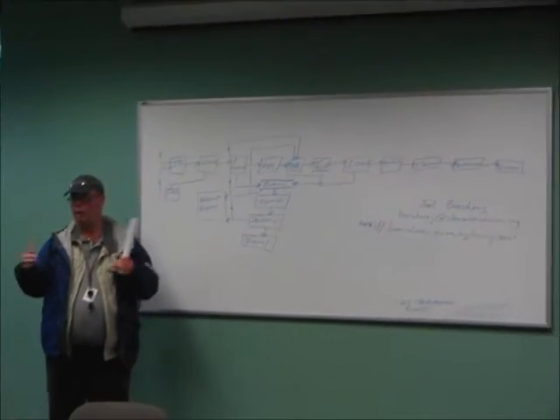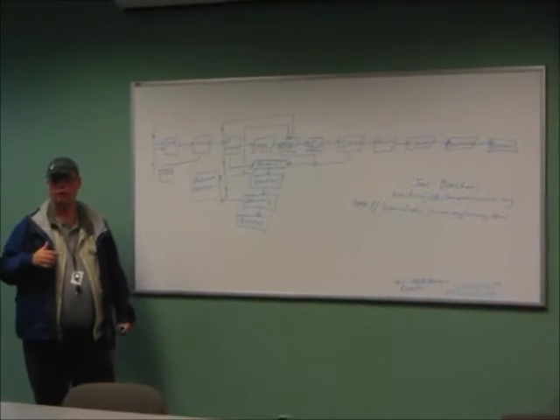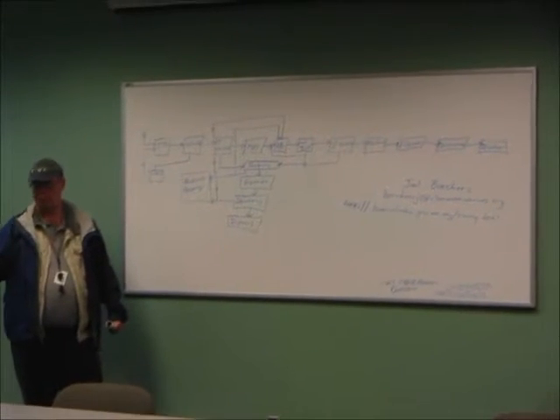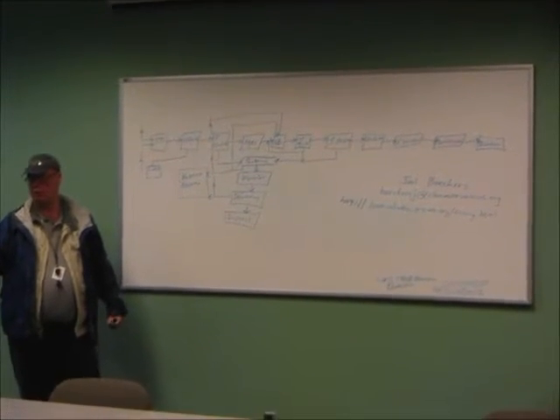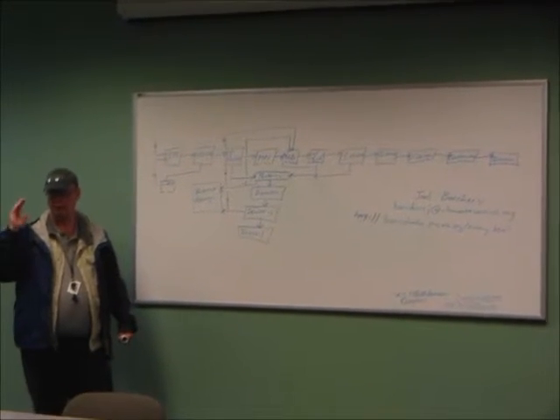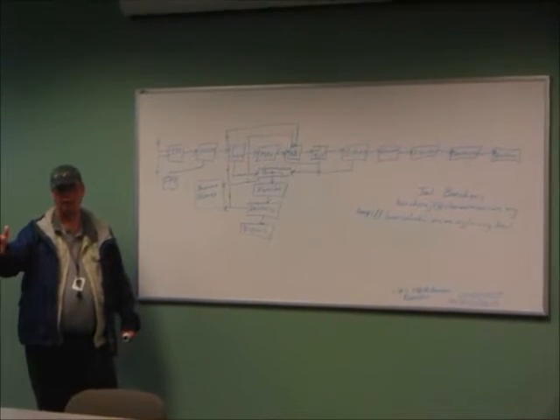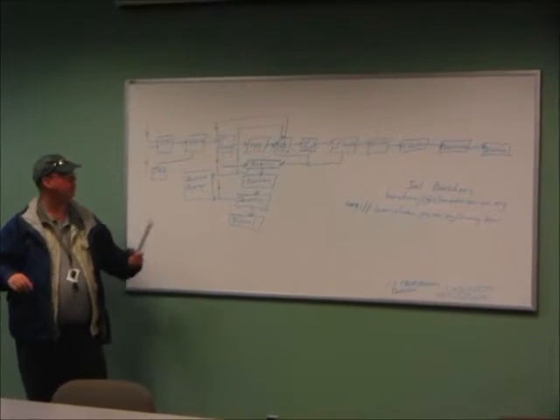We used to split the flow by weirs to 3 aeration basins, and when we added the 4th one, we just didn't quite have enough head to split them evenly. So what we did is we raised the flow up a little bit, and then we could meter the flow to each aeration basin simultaneously. We can split it 25% to each aeration basin, or if we want, we can say we want this aeration basin to get 5 mgd and then split the rest.